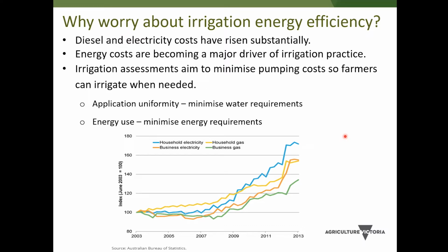But if it's not, and you're compromising your scheduling, so the crop's stressed, the yield penalties will quickly outweigh the energy cost savings. So the assessments that we do are really about trying to minimise those pumping costs for farmers so that you can confidently irrigate when you need to. So we look at application uniformity. So that's about making sure water's going out evenly, and that minimises the amount of water that needs to be applied, reducing water costs and energy costs. The other side is looking at the energy efficiency of the pumping system to reduce overall energy requirements.